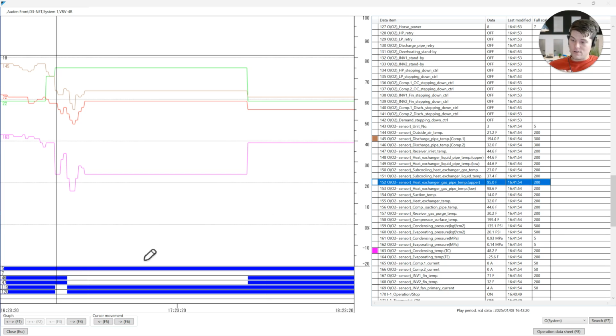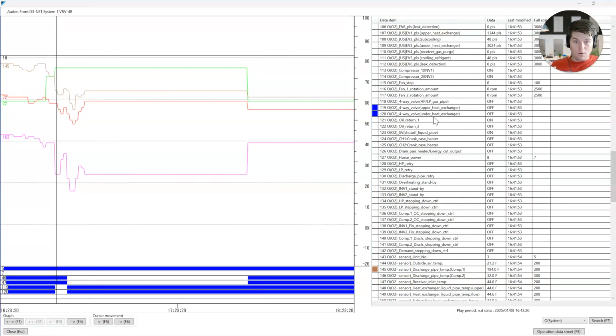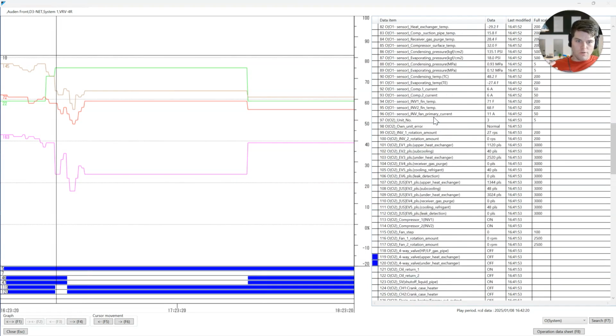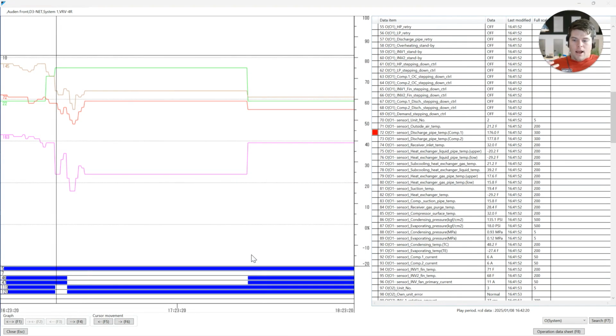95, 98 degrees, okay? This says it's supposed to have hot gas in the outdoor heat exchanger. Is that correct? Bing, bing, bing, bing, bing. It is correct. Okay, those four-way valves have shifted. We're good there. Now let's jog on over to our other module and see how it does in defrost. Let's jump into the middle of here. All right, and we look at this now, 131 and 136. Bing, bing, bing. These four-way valves work.